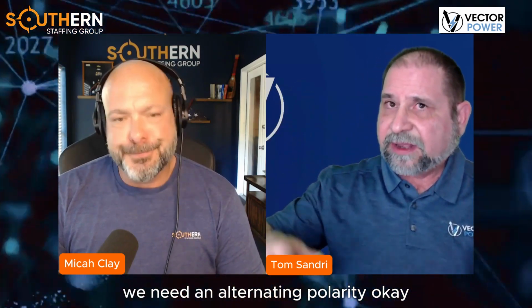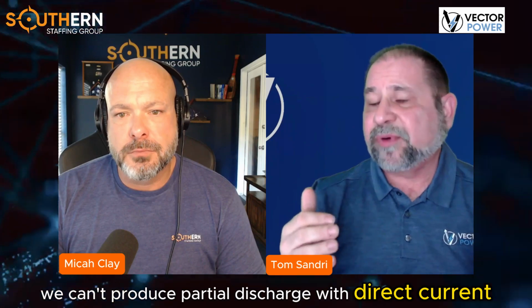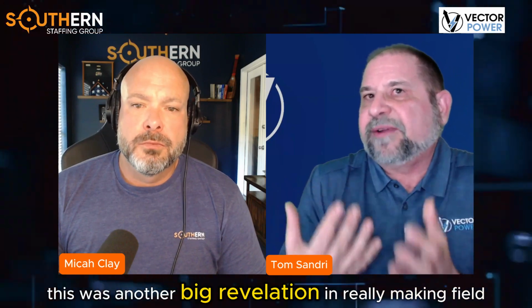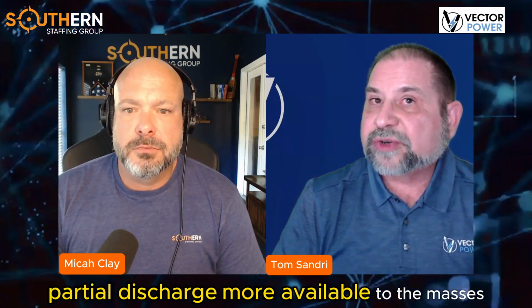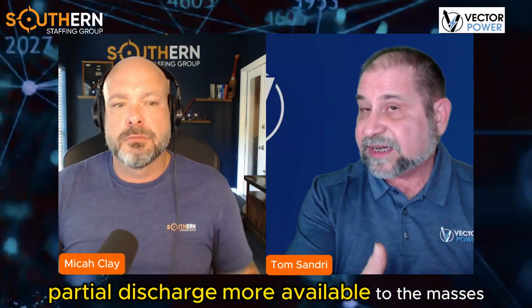Exactly. And then one of the big revelations was, in order to create partial discharge, we need an alternating polarity - we can't produce partial discharge with direct current or DC. So when the very low frequency, or VLF, power supply started to come out into the industry, this was another big revelation in really making field partial discharge more available to the masses.